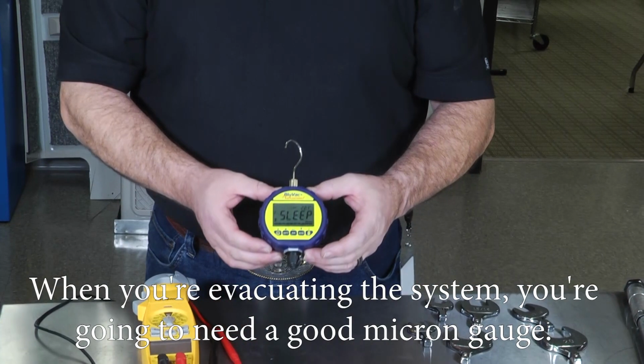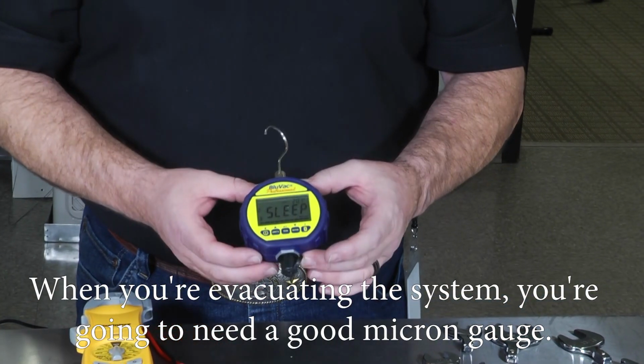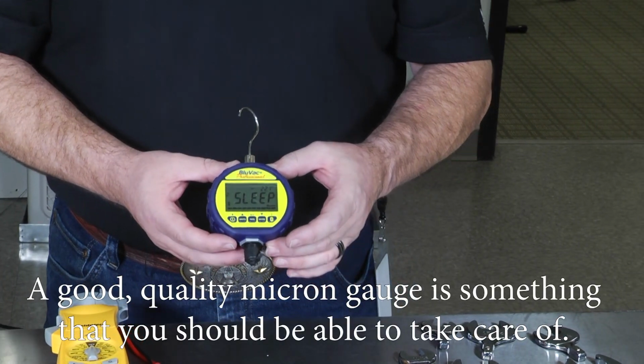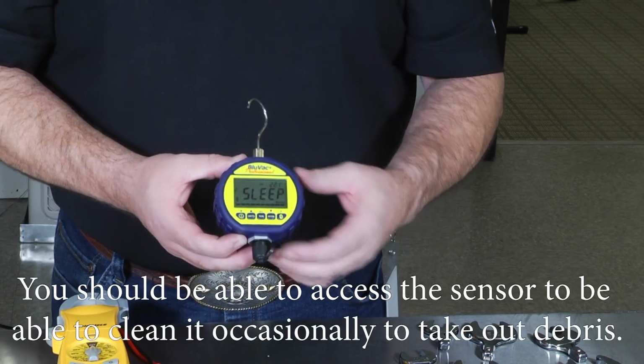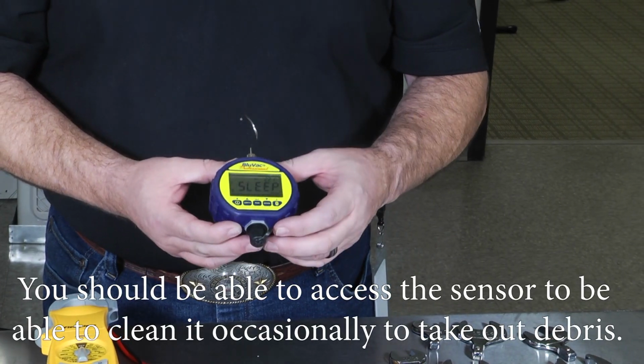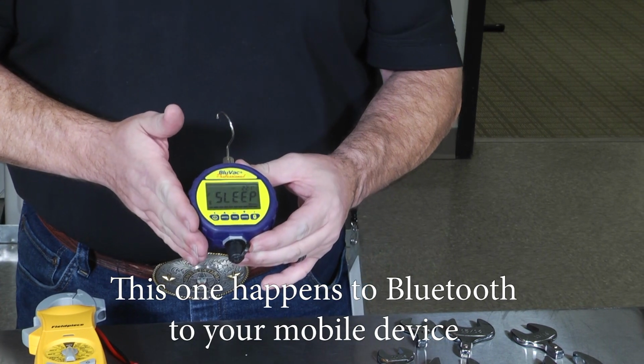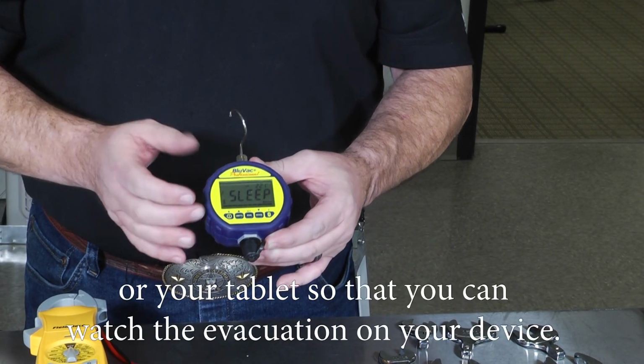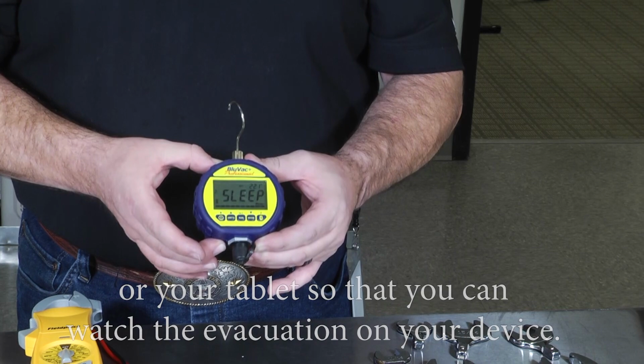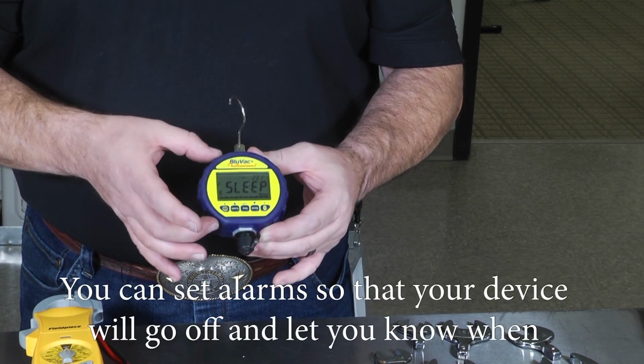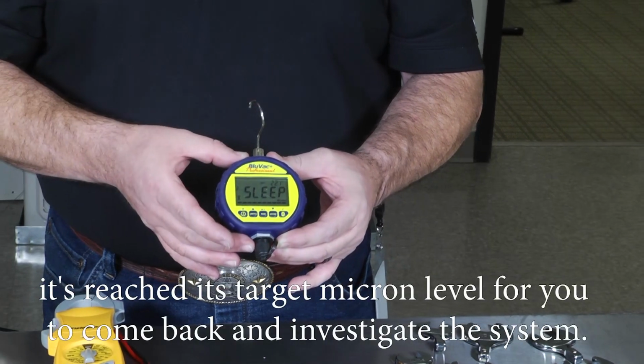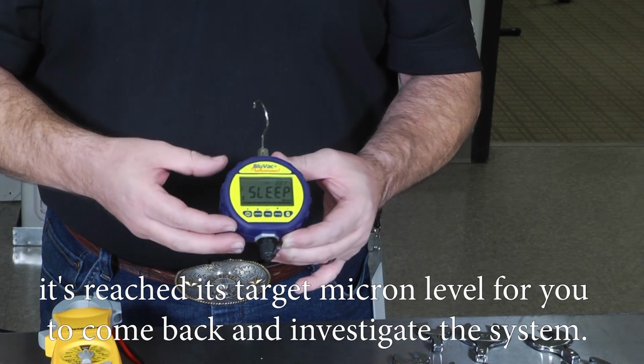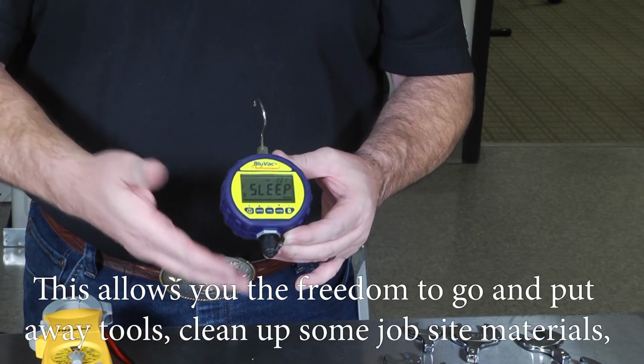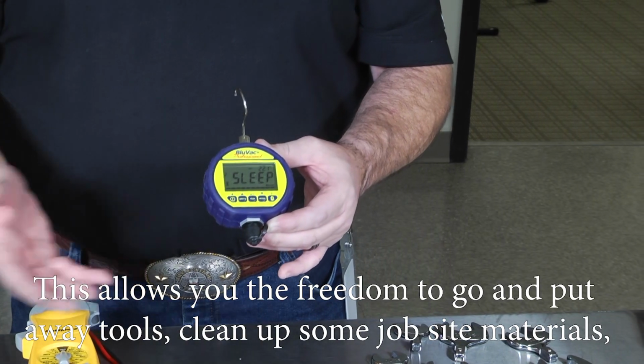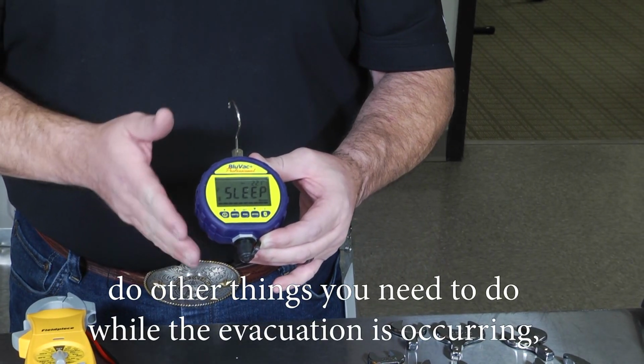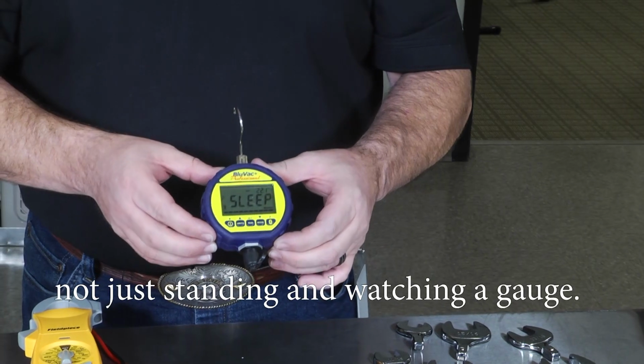When you're evacuating the system, you're going to need a good micron gauge. A good quality micron gauge is something that you should be able to take care of. You should be able to access the sensor to be able to clean it occasionally to clean out debris. This one here happens to Bluetooth to your mobile device or your tablet so that you can watch the evacuation on your device. You can set alarms so that your device will go off to let you know when it's reached its target micron level for you to come back and investigate the system. This allows you the freedom to be able to go and put away some tools, clean up some job site materials, do other things you need to do while the evacuation is occurring. You're not just standing and watching a gauge.